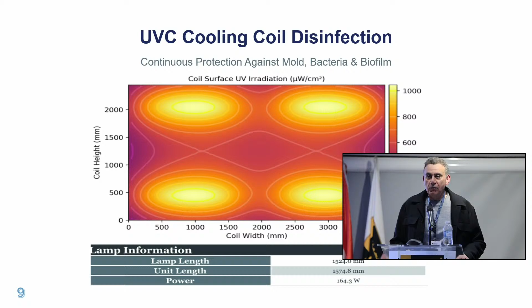So the program gave us an output that says for this large coil, you need 4 lights. Each one is, I think, 154 centimeters long, and each lamp is 164.3 watts to do the proper disinfection according to ASHRAE 185.2. Now, this is a cross-section. On the right-hand side is the actual lamp that was installed, 4 of them. On the left-hand side is a cross-section through the coil.